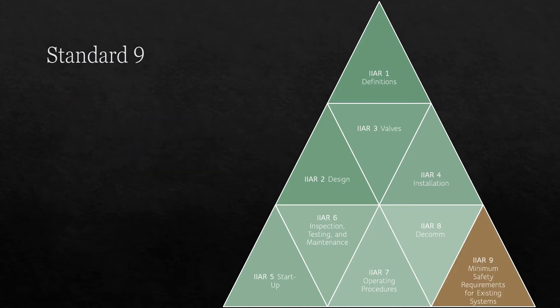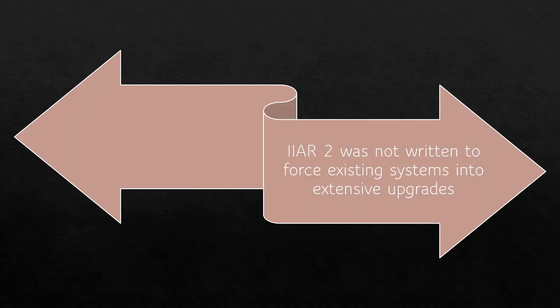The title of Standard 9 is Standard for Minimum System Safety Requirements for Existing Closed Circuit Ammonia Refrigeration Systems. Like all other IIAR standards, Standard 9 was published to address a specific need in our industry. The motivation for writing a standard for existing systems was two-fold. On the one hand, we wanted to prevent IIAR's design standard, Standard 2, from being used as a regulatory weapon against systems built before that standard was published.